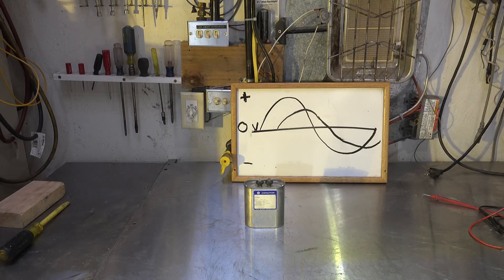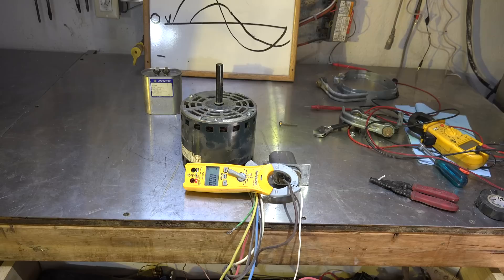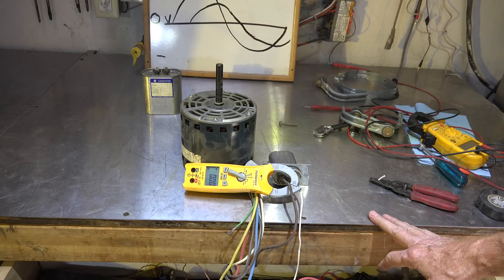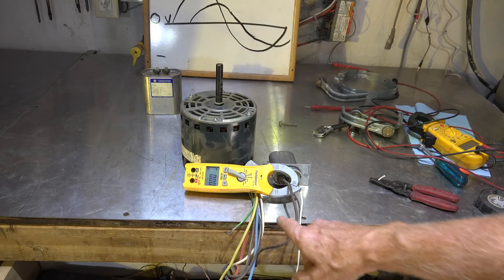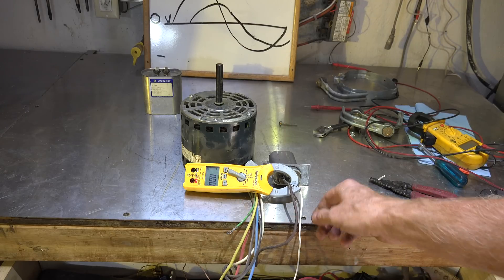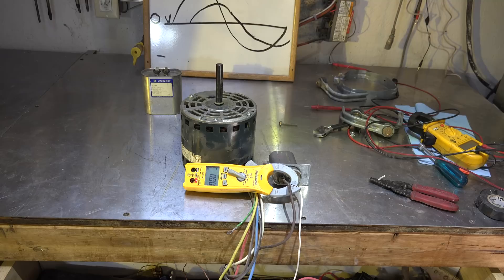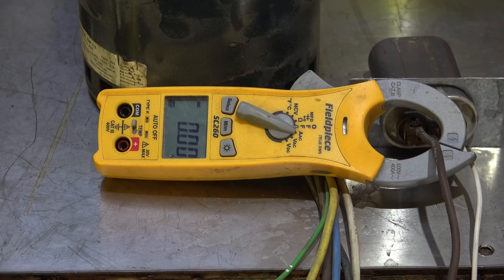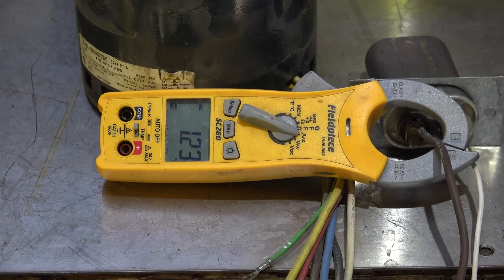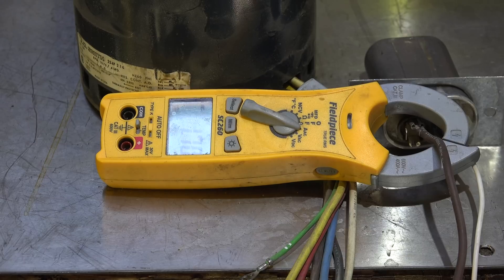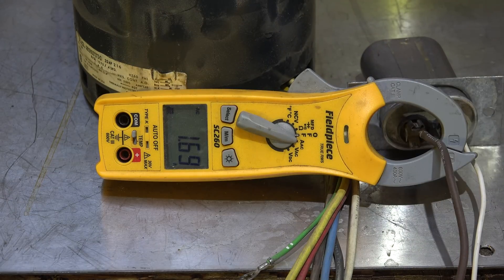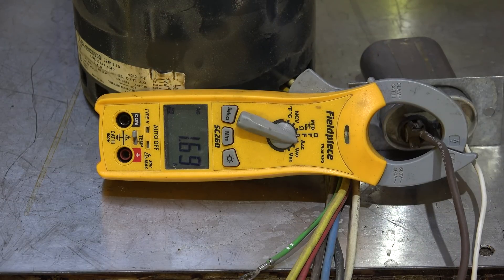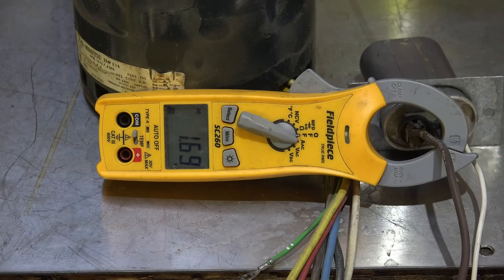Here I'm set up with a motor - PSC motor. It has a run cap on it, and I've clamped the run circuit through the capacitor. Let's see what kind of amp draw we get. Okay, we're going to start the motor. Okay, we're drawing about 1.7 amps through the run circuit.